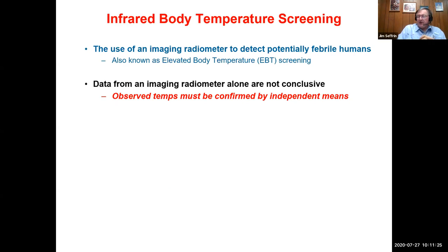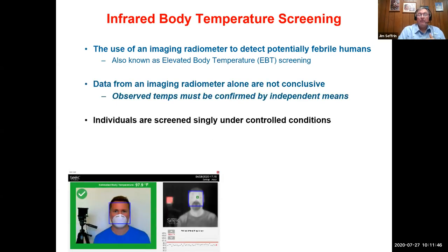It must be understood from the outset that data from an imaging radiometer alone are not conclusive. Therefore, observed temperatures must be confirmed by independent means in order to meet the protocol set forth by the FDA and the International Organization for Standardization, or ISO. In order to perform infrared body temperature screening properly, individuals are screened singly under controlled conditions.